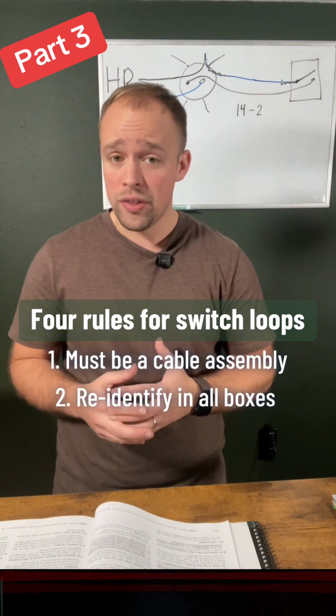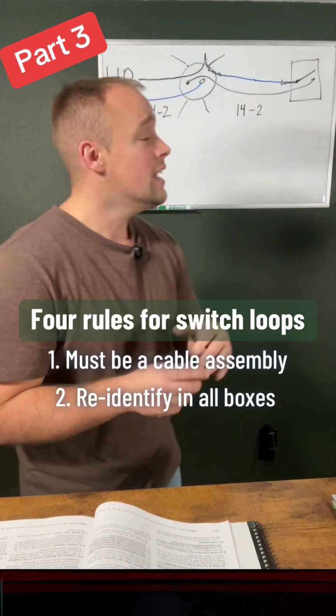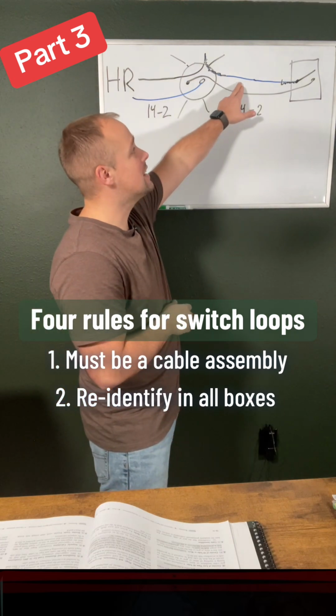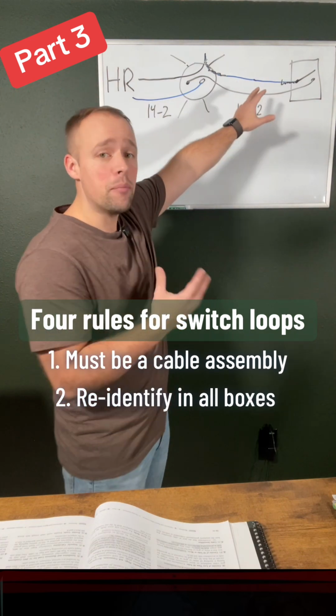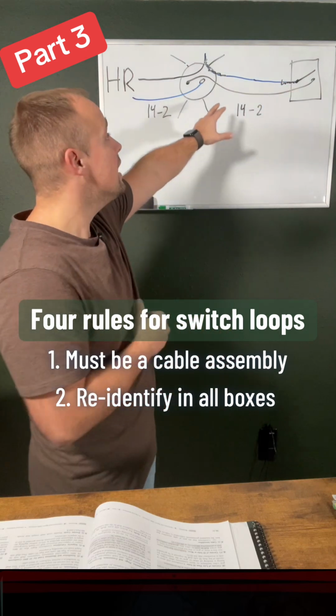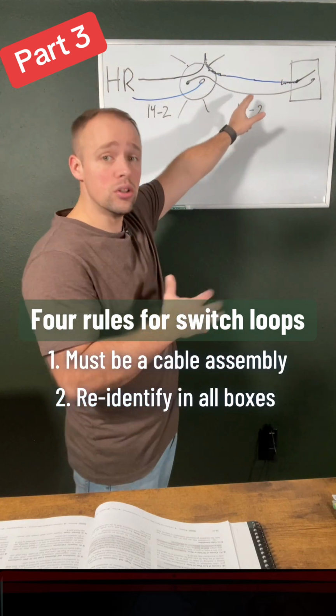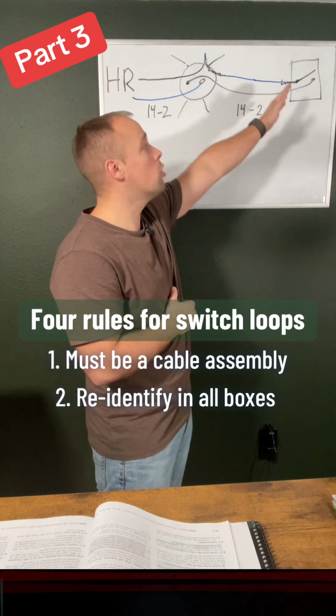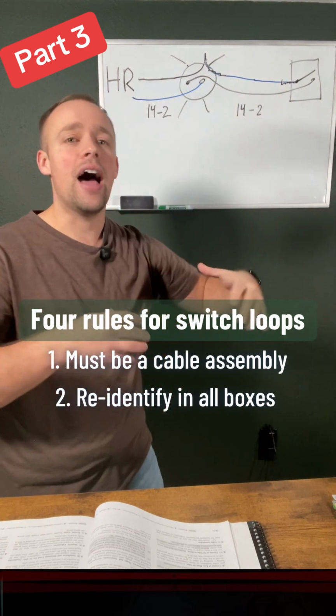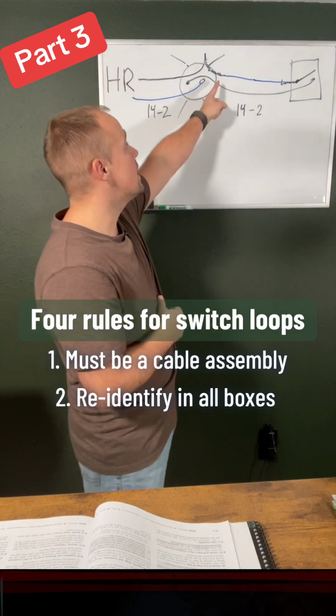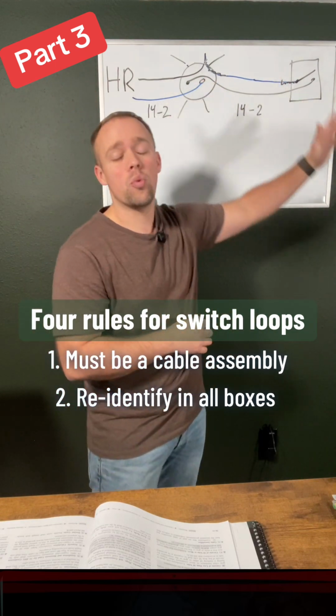The second rule that you can see in this same code article is that that white insulated conductor that again is not being used as a neutral, it's used as a hot. It has to be re-identified to look like a hot at every termination and location that it is present in. So that's why I re-identified it in this light box as well as this switch box. Okay, what are the other rules?